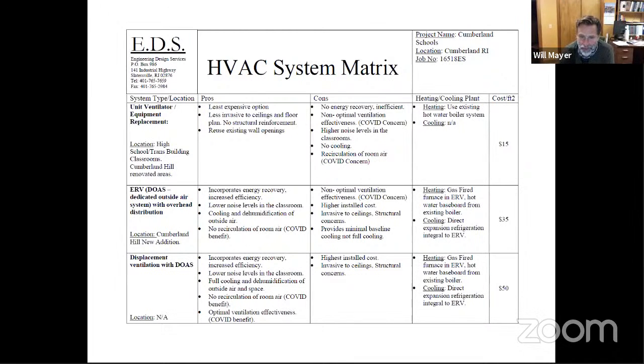Yeah, those are basically two forms of disinfection that have been recommended by ASHRAE, and we've seen them going in quite a bit. We find that the bipolar ionization tends to be more effective just because it's actually sending the ions out into the space where they can do work, whereas the ultraviolet option only sees the air that goes past it. It has to be concealed, usually within the ductwork or within the unit. And there are some systems that combine both of them, which is a win-win.